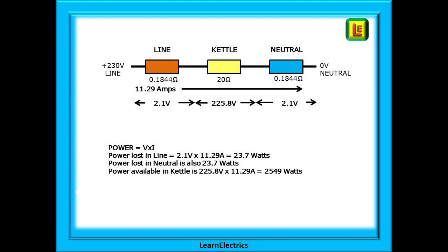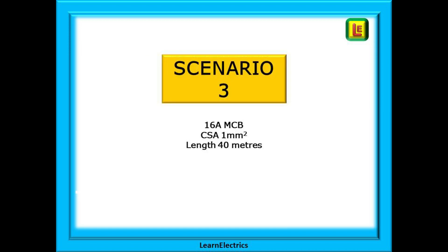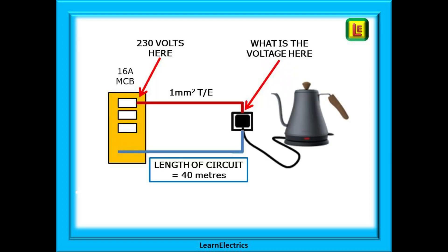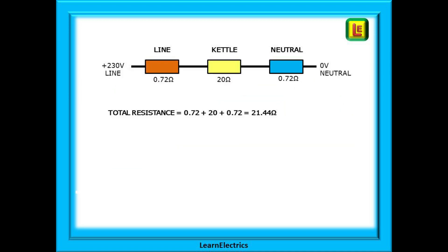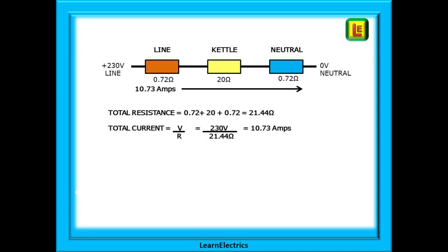Scenario three: a single socket at the end of a 40-meter cable run. An unthinking electrician has used a 16-amp breaker and one-millimeter twin-and-earth cable — using up a half-empty reel from the van. The resistance of the line and neutral is 0.72 ohms each, based on 40 meters of one-millimeter copper. The kettle is still 20 ohms, giving a total resistance of 21.44 ohms. Current is 230 volts divided by 21.44 ohms = 10.73 amps. The thinner cable has had a noticeable effect on current.